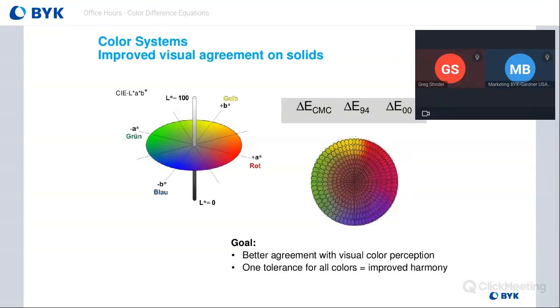To capture sparkle, how much lux is necessary for the light source? So the good news is within the instrument, the light source is fairly bright and the measurement time is fairly short. And we take care of calibrating all that out for the camera and the light source technology in the instrument. So you'll always have enough light source or lux in the instrument to capture it.